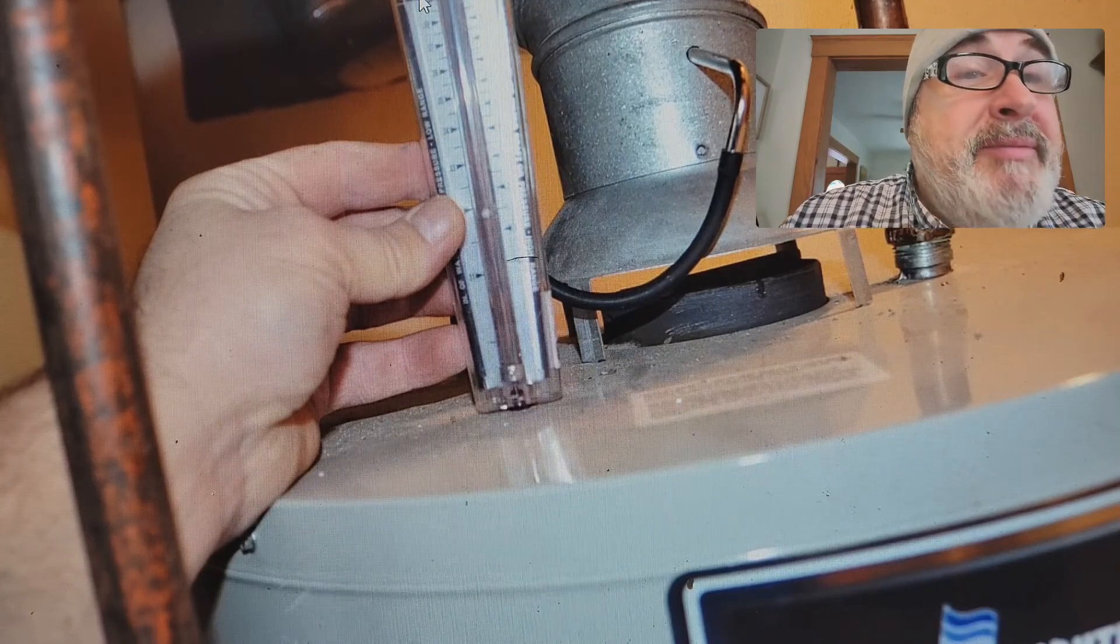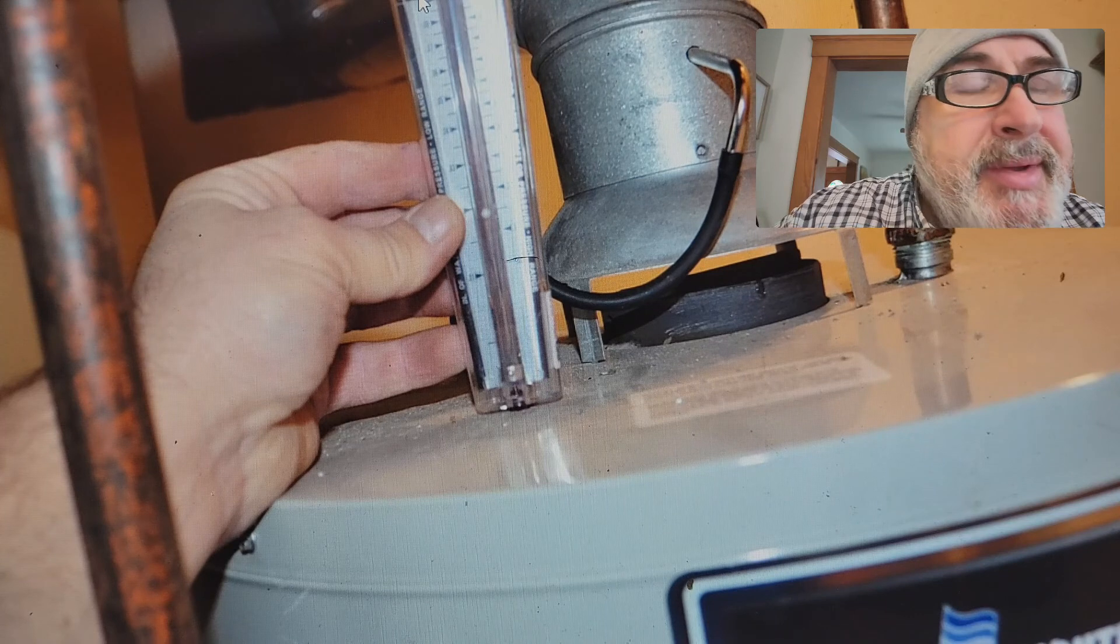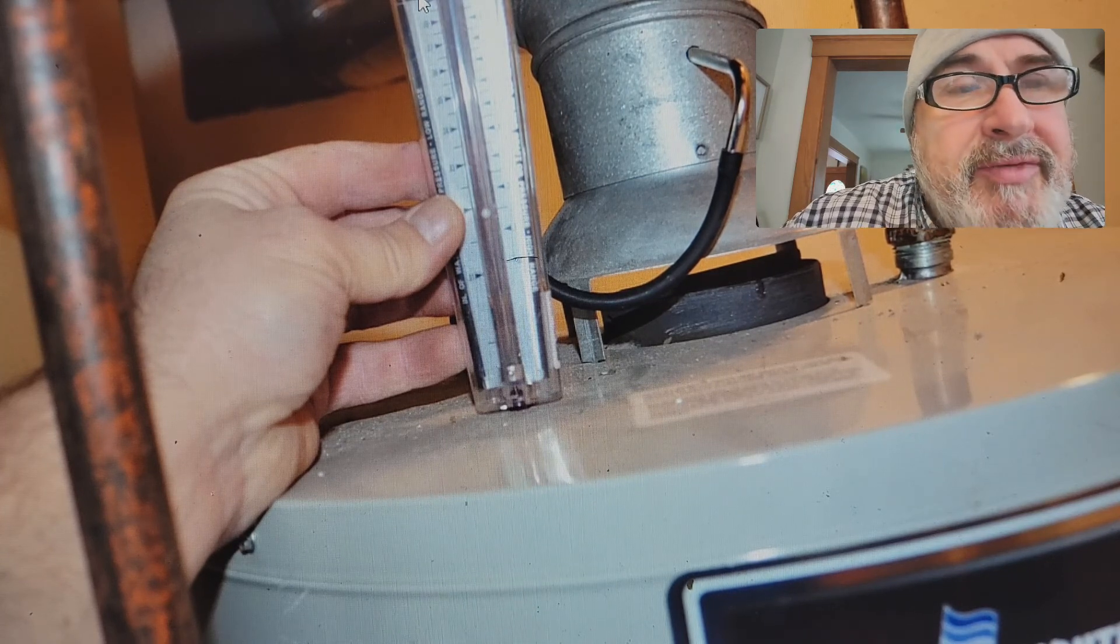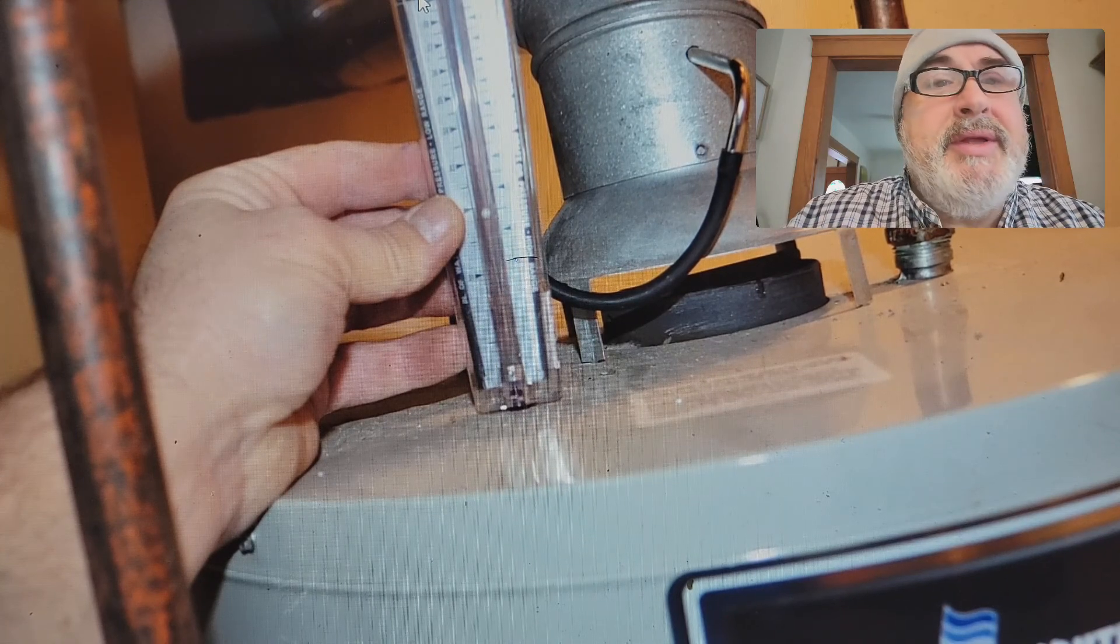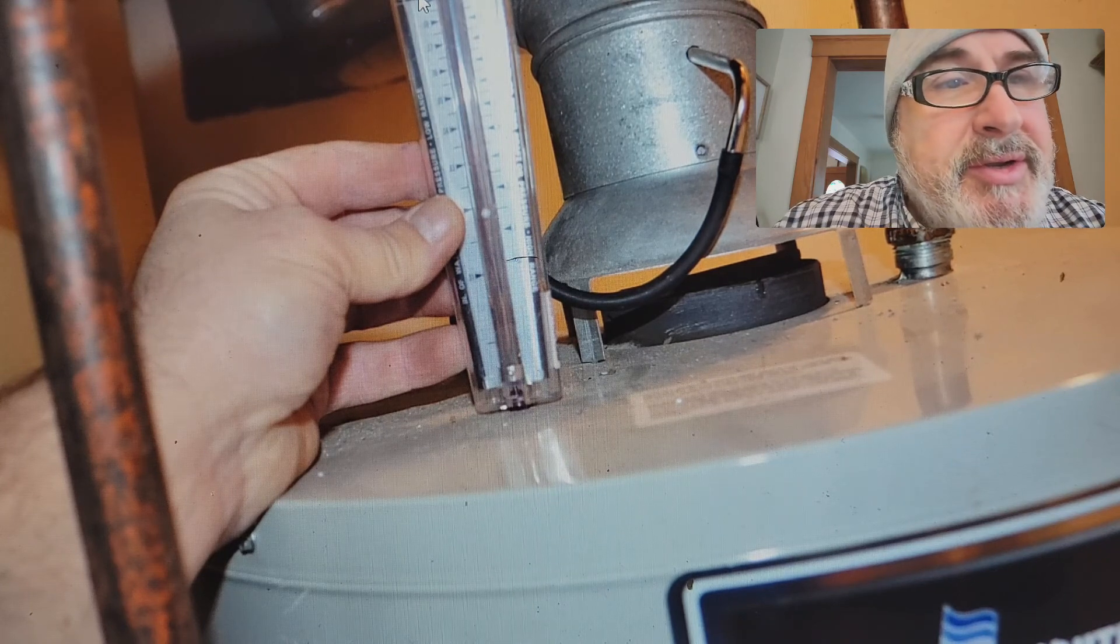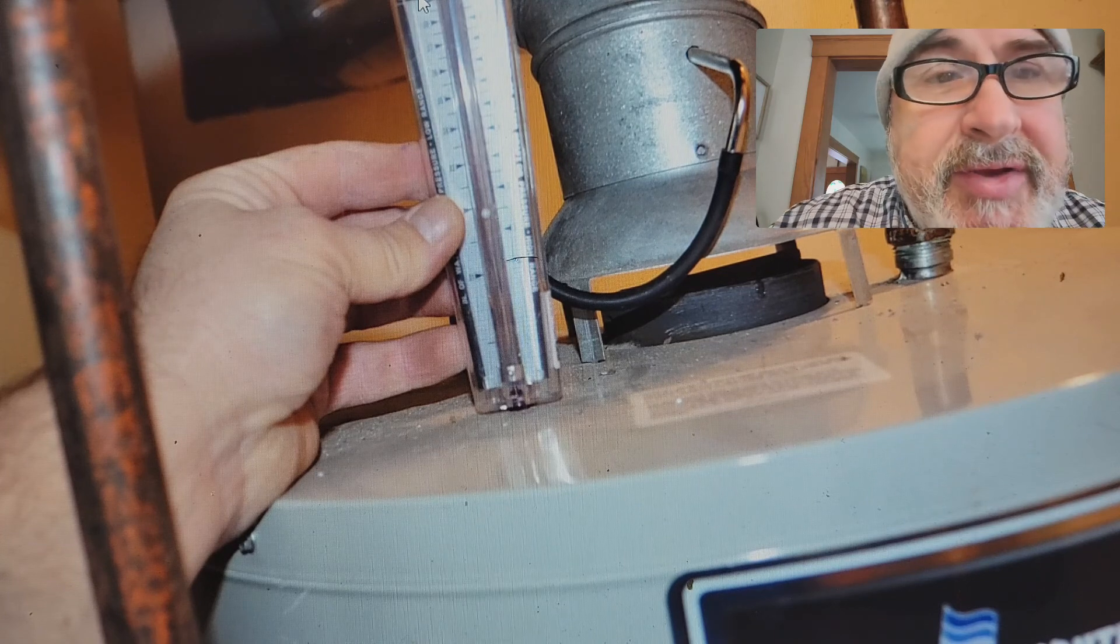Now, negative draft means the air is coming back down. And you could easily do that by, let's say, a house fan up in your attic. You turn the house fan on and don't have open windows. Boom, you got negative pressure. It screws it up. And so the whole house draft thing, fireplaces affect it, fans affect it, opening, closing windows affect it.